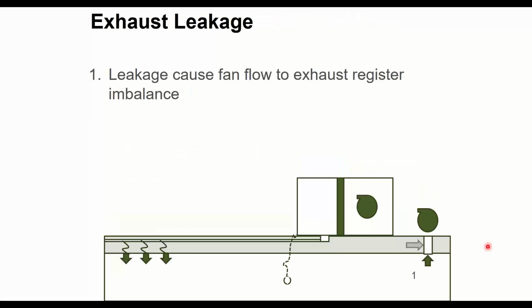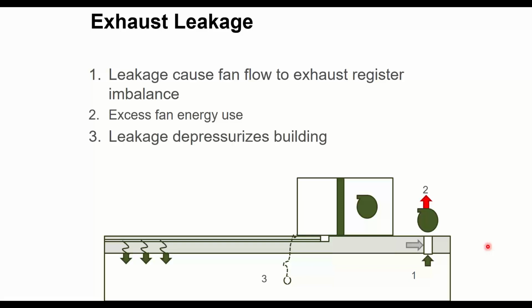And then as I mentioned with exhaust systems too, if you have duct leakage there, this is a really tiny duct on this drawing, so it's kind of crappy. But most duct systems have much longer runs for exhaust shafts. This one's only like 7 feet long. But that leakage duct out there does change the pressure relationship with the building. It does cause air to leak into those spaces sometimes if I have leaky ductwork, right? So I'm supposed to be sucking a certain amount of CFM up this duct and out this fan. And this fan's moving whatever. Say it's moving 5,000 CFM. It may only be getting 3,000 from the space. And 2,000 might be coming from the leakage of the shafts, which puts this whole shaft, the ceiling cavity, under a negative, which means somewhere else air is leaking in to take care of that. So I have quite a few penalties there.